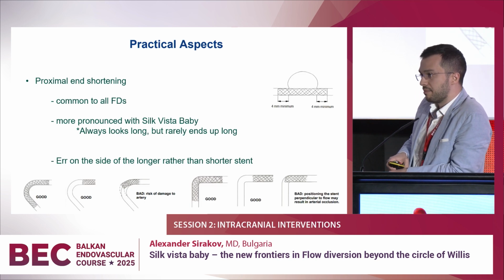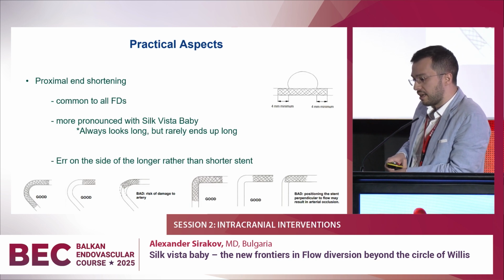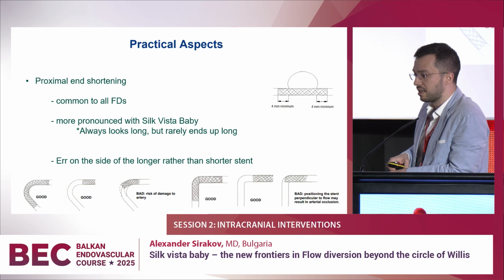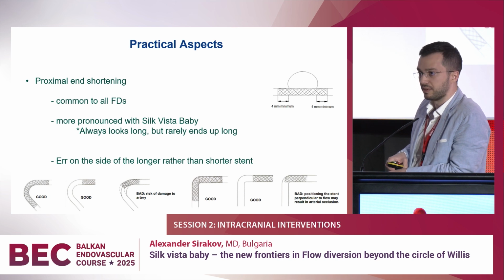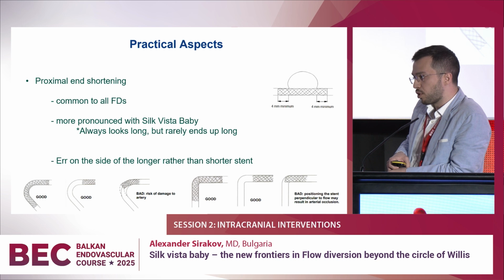Some practical aspects and maybe some technical considerations about this stent. You should be aware of some proximal shortening, but that's a common feature for the majority of the flow diverters, maybe besides the FRED.